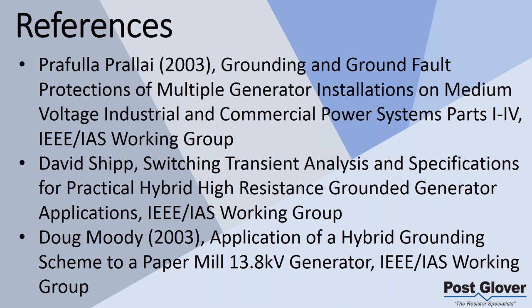Stephen in Indiana said, I have seen 60-second rated resistors for the 10 amp high resistance grounding. Is a 30-second rating okay, or is it safer to stay with 60 seconds? It really just depends. If you don't feel like 30 seconds is enough time for your system to completely shut down, and that includes literally your entire generator coming to a complete stop, then please don't do it.